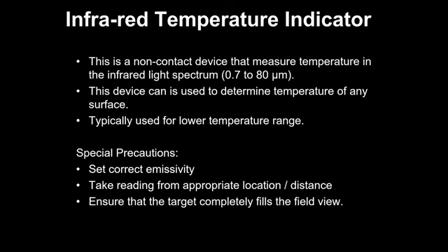So you need to correctly select the emissivity. That's the most important thing. The location should be correct, because as the distance increases, the total target window increases. If you're taking a reading from a long distance, the total surface area being read becomes very large. If you cannot go very close, the reading may not be correct. That is what we need to be careful about, and it will also be indicated by the OEM, that these are the values, and the target should completely fill the view.